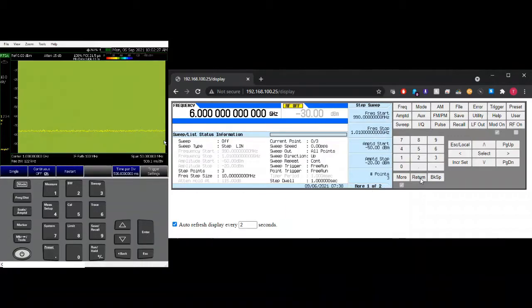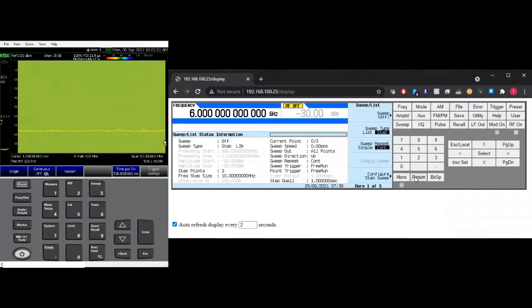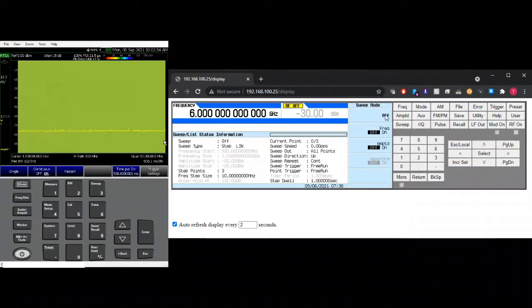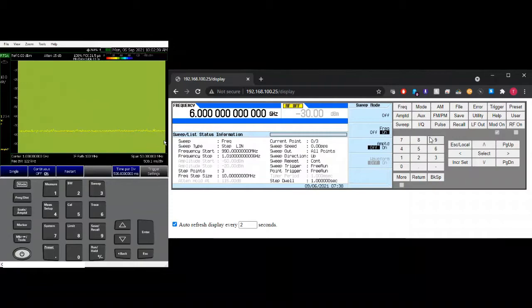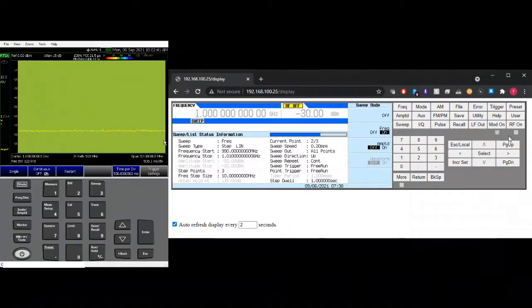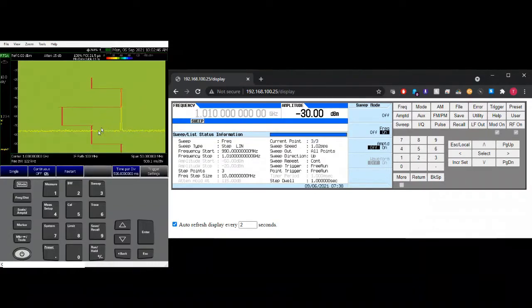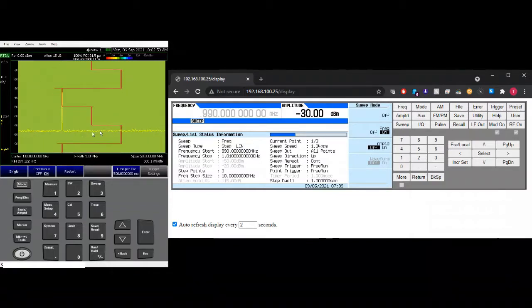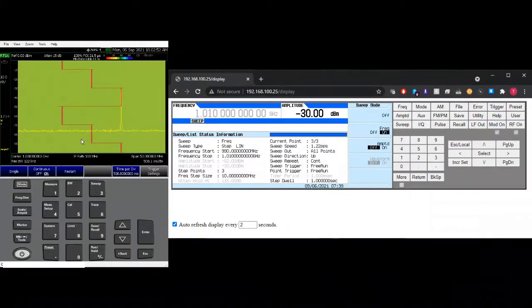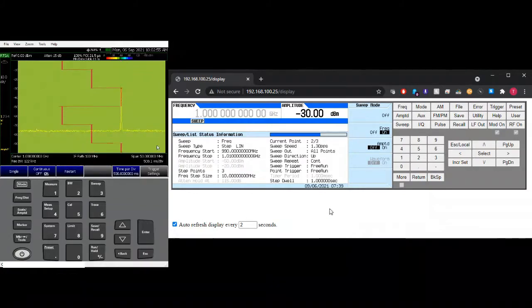So once you're happy with this setup, this is a summary. It's on free run. And then we can go to sweep here. So we want to sweep frequency. Let's start with sweeping frequency first. So let's turn on the RF. So as you can see, it is 990 meg, 1 gig, 1.01 gig. So this is just a cutoff from one frequency to another.